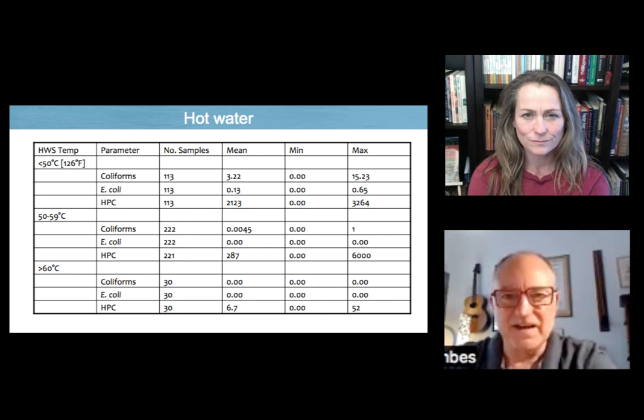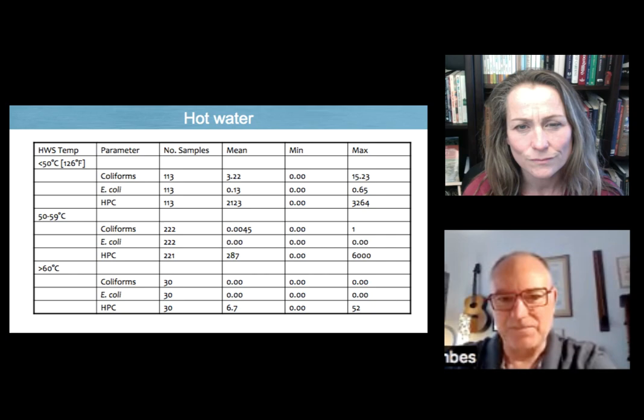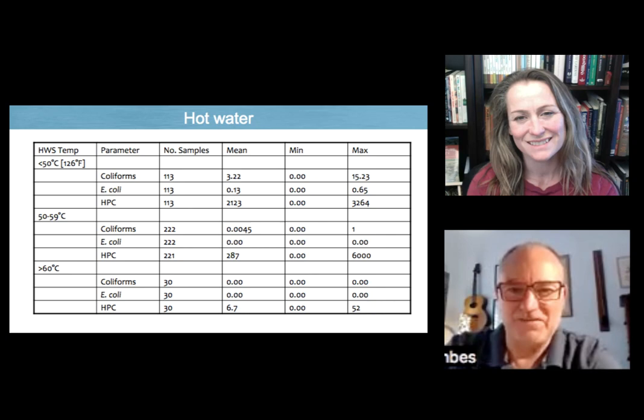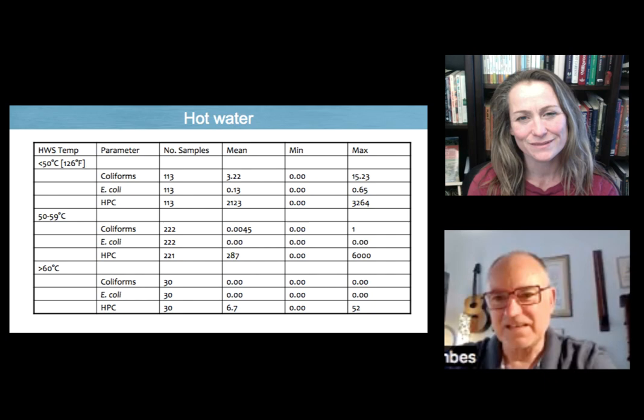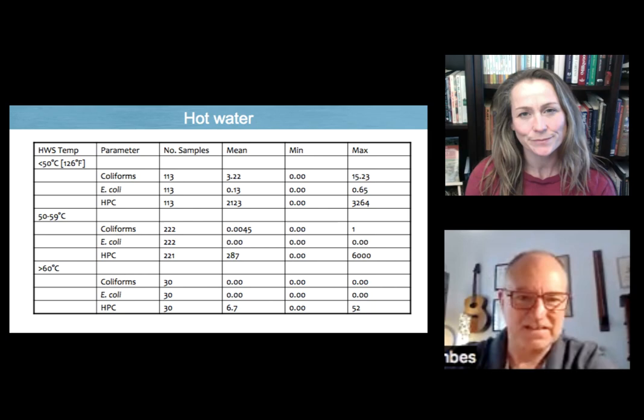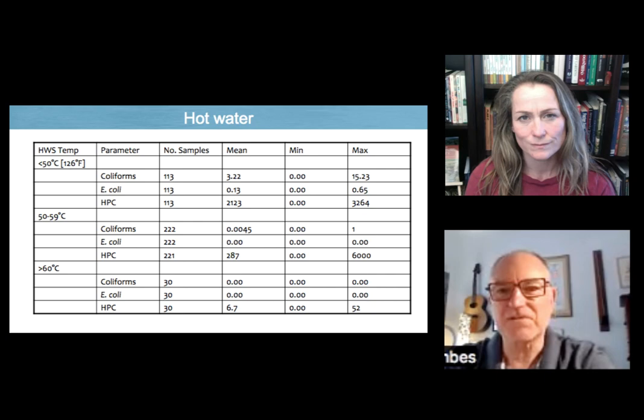So if you then go down to between 50 degrees and 59 degrees Celsius, you can see the mean results from the testing is reduced to very, very small numbers. You know, 0.0045 of a coliform. And you can see even the maximum results is one count of a coliform and none of the E. coli and 6,000 of heterotrophic plate counts. But bacteria is in all water. We're concerned about pathogens. So it's removed the majority of the indicators of pathogens. But I'll come to that in a second.